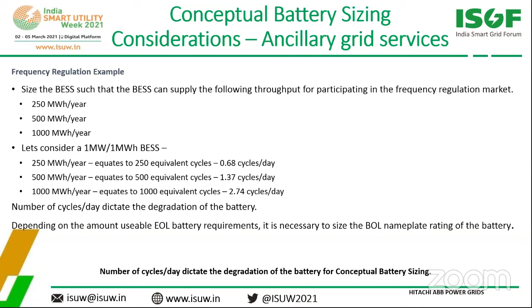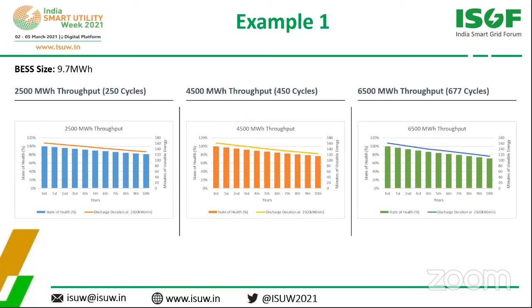This particular slide tells you when we have the requirement for 10 years life, the utilization and state of health, how the sizing can give you the requirements of number of cycles to be in operation. This case is with respect to 7.3 megawatt hour. The other case is when you size the battery based on the requirement studied from the regulator or system operator, you can come up with the exact sizing to meet their requirements. So sizing the battery is of real importance in terms of understanding the requirement and coming up with the proper sizing to meet the requirements of the network.